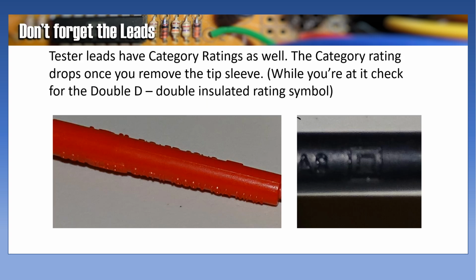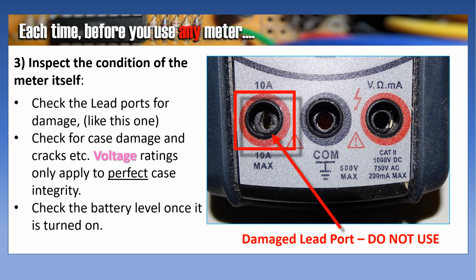Tester leads have category ratings as well. The category rating drops once you remove the tip sleeve. And while you're at it, check for the double D or double insulated rating symbol on the actual leads themselves. So we talked earlier about each time before you use any meter, and we got to step 3, inspect the condition of the meter itself. Absolutely. Things change. Things get dropped, broken, etc.